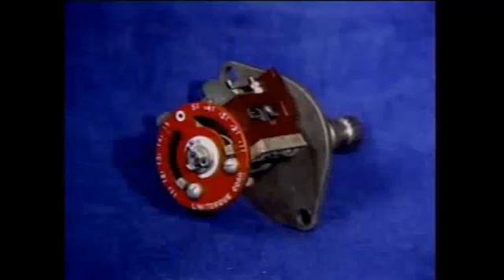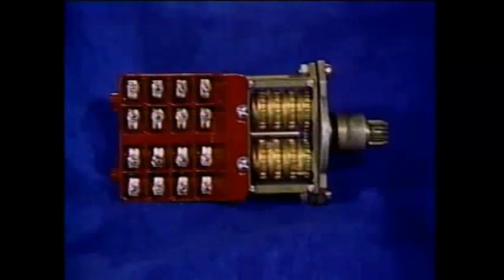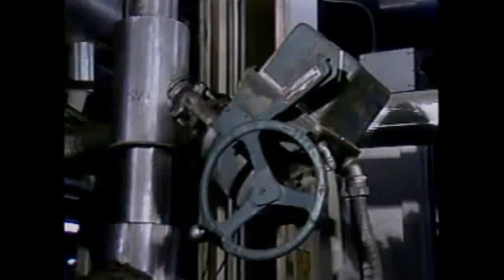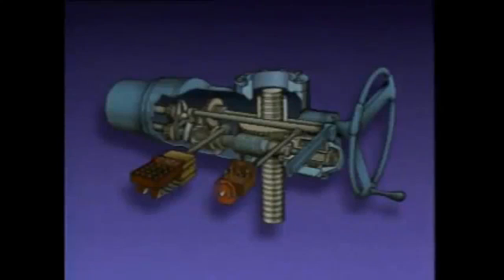If an obstruction blocks stem movement in a valve, a properly set torque switch can cut off the motor before damage occurs. While a torque switch cuts off current when turning force reaches a preset amount, a limit switch cuts off current when a valve reaches a preset position — for example, shutting off current when the valve is fully open. Even though a motor operator consists of many components, it's usually represented by a single symbol on a piping system diagram.